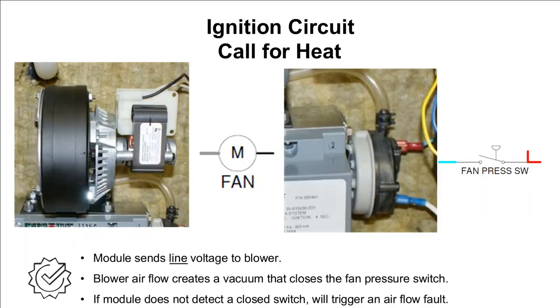So what does the module do at this point? Well, the first thing it's going to do is send line voltage to our blower. The blower is going to engage. The airflow creates a vacuum which closes this fan pressure switch, which is located on the right-hand side of the ignition module. The module is looking for a completed signal through that switch. If it does not see the signal, it will go to lockout. It will stop ignition, and you will see a single flash code on the module LED. This signifies airflow fault. Either the fan switch is not closing, or there's some other problem going on there.